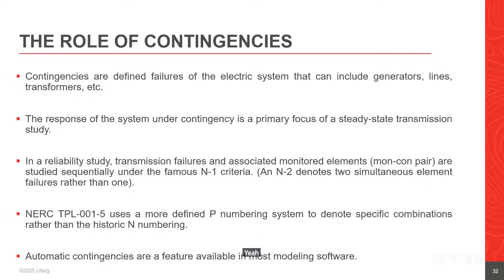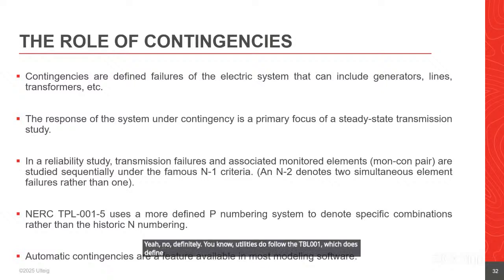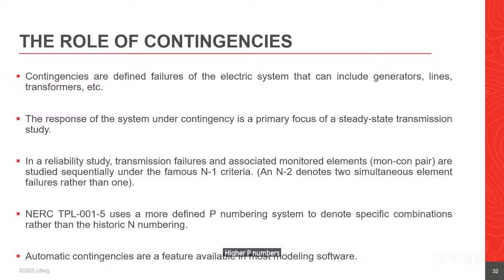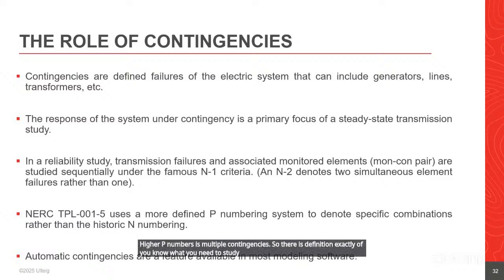Yeah, no, definitely. Utilities do follow the TPL 001, which at a high level defines and tells you what needs to be studied as a contingency or an outage under P0, which is no contingency. P1 is a single element, and if you get into the higher P numbers, it's multiple contingencies. So there is a definition of exactly what you need to study to simulate. One example would be a P1, and within it you have a P1.1, a P1.2, P1.3, P1.4.